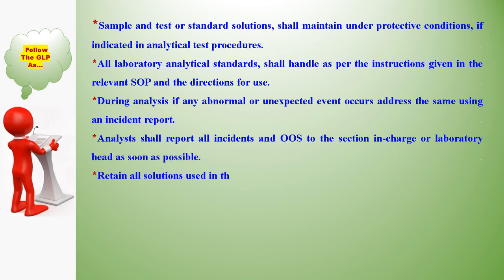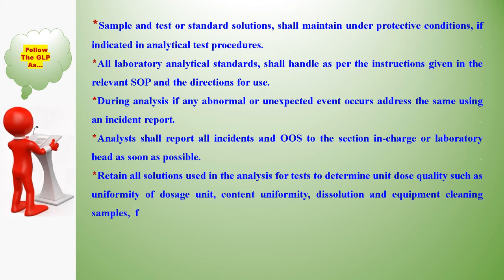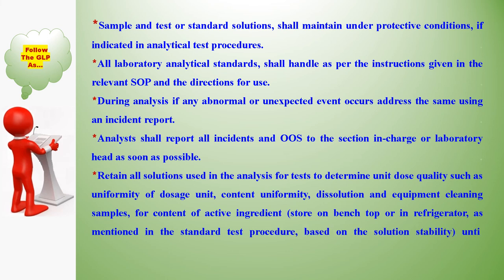Retain all solutions used in the analysis for tests to determine unit dose quality — such as uniformity of dosage unit, content uniformity, dissolution, and equipment cleaning samples for content of active ingredient — store on bench top or in refrigerator as mentioned in the standard test procedure, based on solution stability, until analytical results are determined, so as to facilitate incident or OOS investigation.